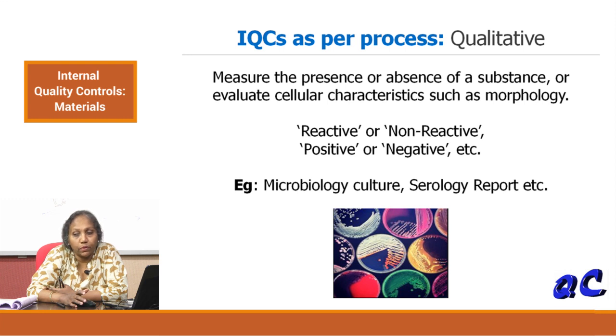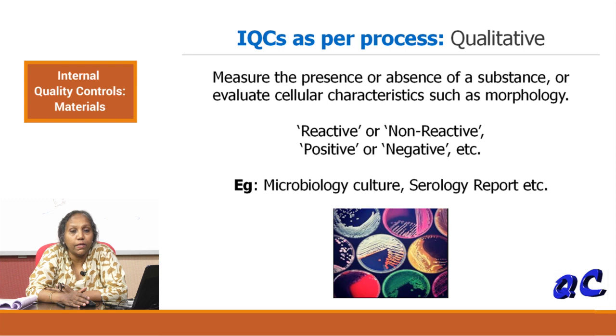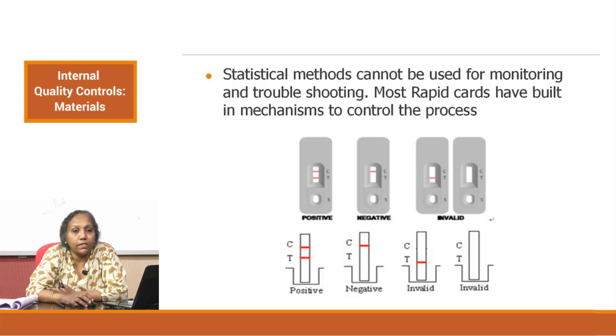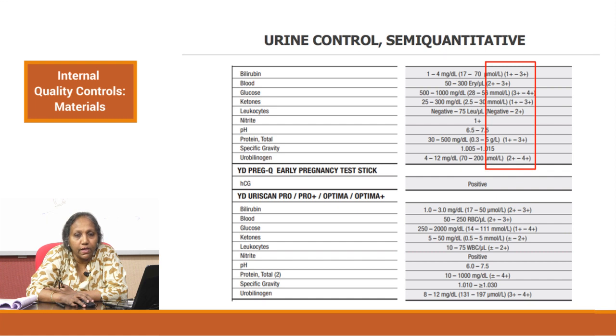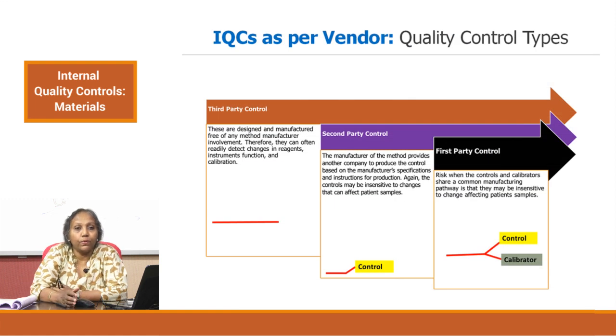The mechanisms of quality assurance for qualitative tests are different and are addressed in a quality control volume 2 module on the website — please read through it to understand the quality assurance procedures that can be employed in qualitative tests. Rapid cards are also qualitative tests, but they have built-in mechanisms of control process — all of us are familiar with the positive, negative, and invalid result format. Semi-quantitative tests are similar to qualitative examination, but QC procedures can be aligned to this kind of testing. Urine controls are an example because reports are given as 1+ and you can quantify the results, with targets given as 1+ to 2+ or 2+ to 3+.